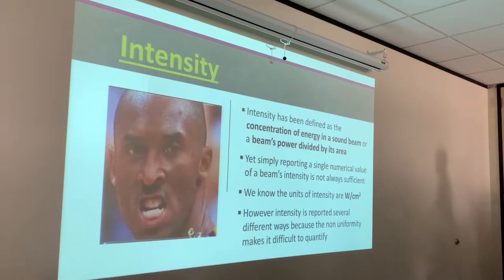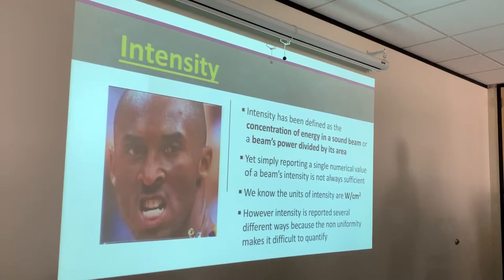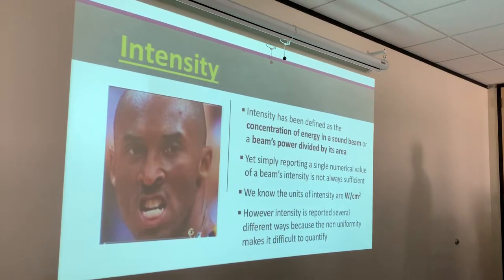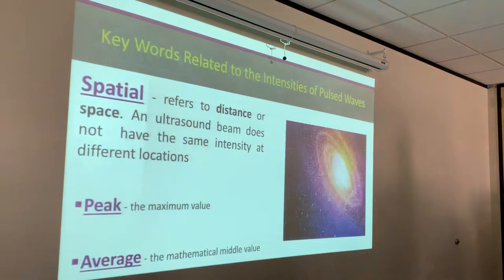Intensity has been defined as the concentration of energy in a sound beam, or a beam's power divided by its area. Units of intensity are watts per centimeter squared. Simply reporting intensity as a single numerical value is not always sufficient because the intensity of the beam is not the same over space and time. Intensity is reported in different ways because non-uniformity makes it difficult to quantify. If I measure intensity right at the transducer versus 10 centimeters distal to that, the intensity will be different. The time and space matter when talking about intensity.